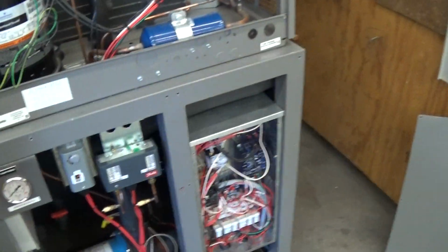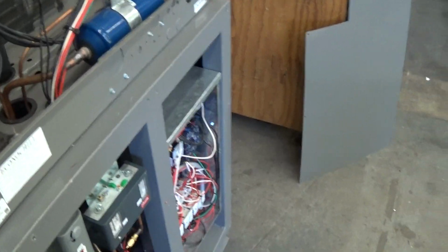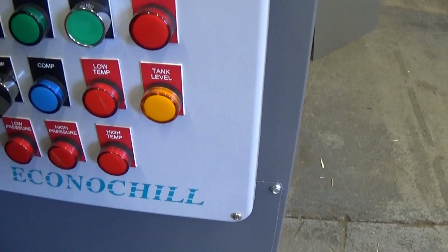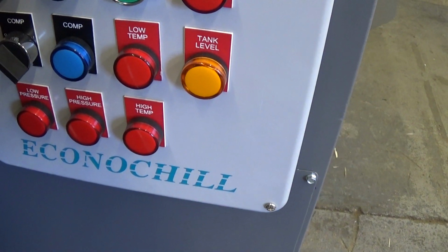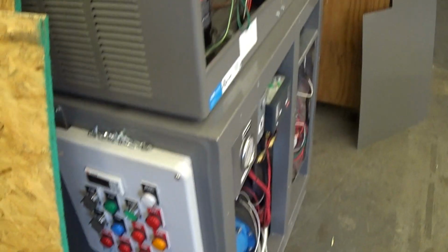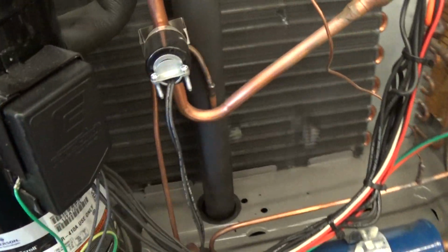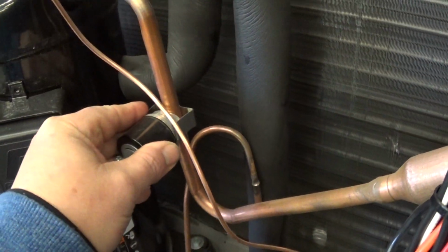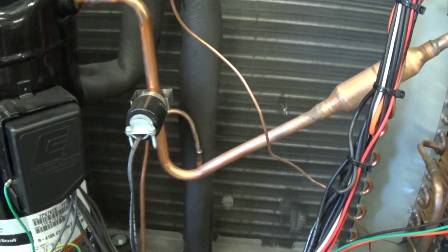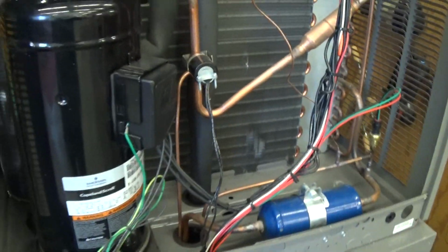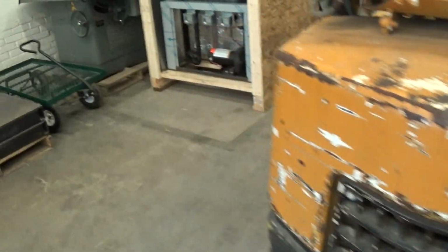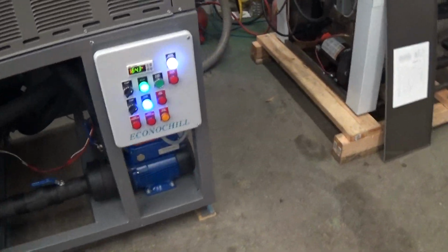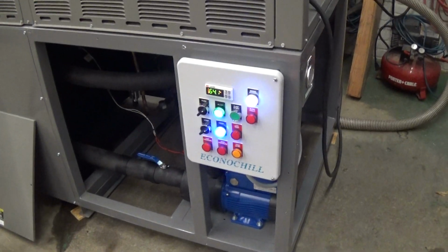On some of the smaller chillers, we have one additional light called high temp, and that's in case the compressor starts operating at a dangerously high temperature. So we have this sensor here on the refrigerant line that will turn the system down. Very rarely do we see that, but it's a nice safety feature that would prompt some attention if the compressor starts overheating. So that's video number 3, and we'll come back to video number 4 as we reach set point here.